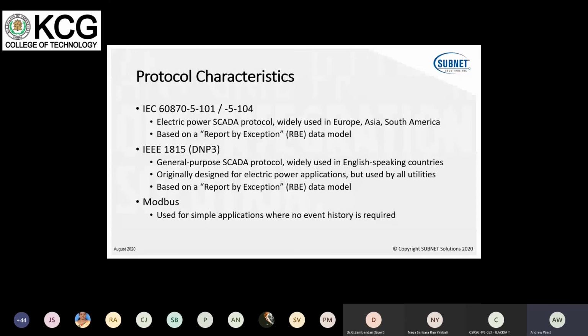IEEE 1815, or DNP3, is the equivalent SCADA protocol. It's used almost universally in North America, Canada, the US, and all of Australia. It's used in the UK distribution system. So I say it's a largely English-speaking country protocol. It's used in about 30% of utilities. Originally designed for electric power applications, so it does the same kinds of things as 101 and 104, but it's a general purpose SCADA protocol and is very widely used in the water industry as well. Again, based on the report by exception model.